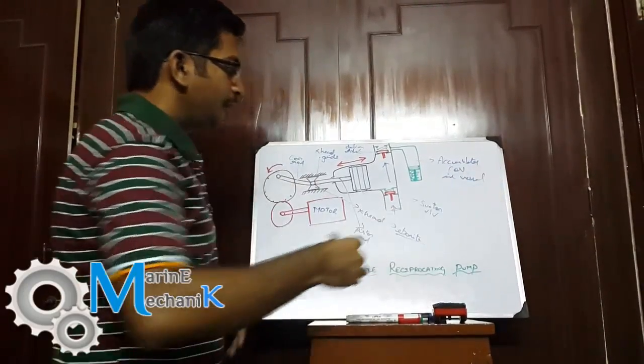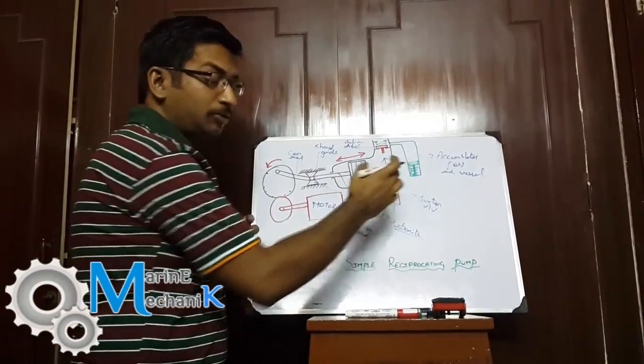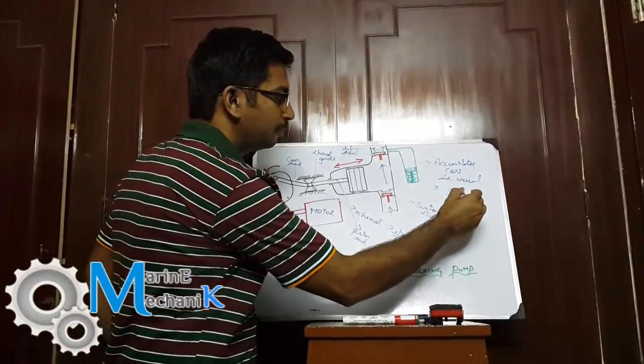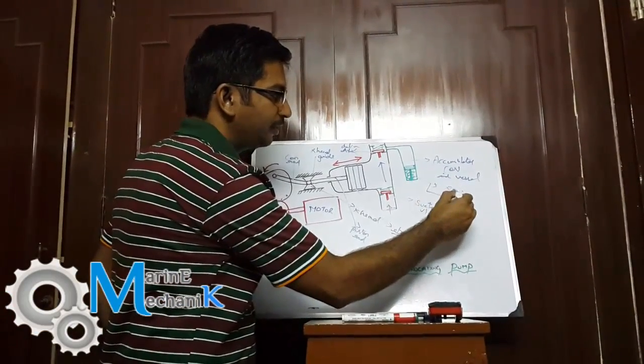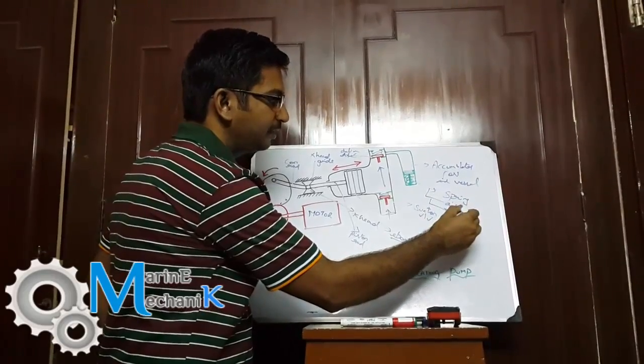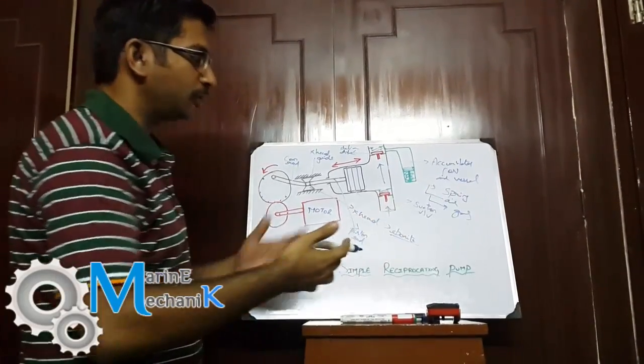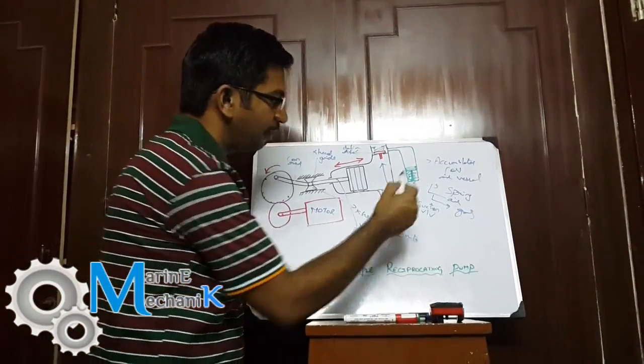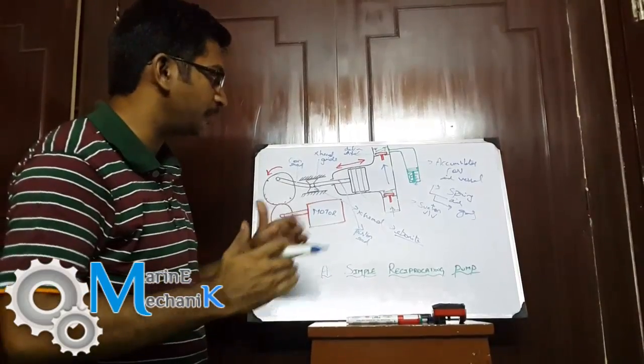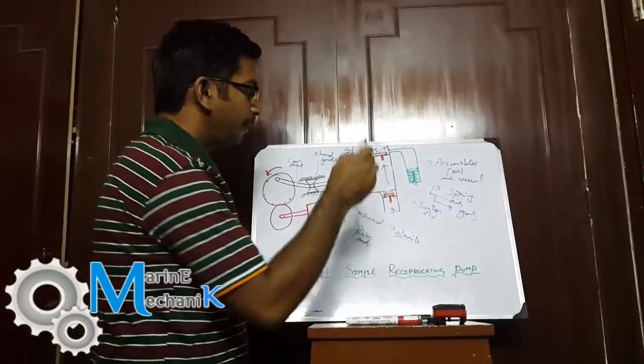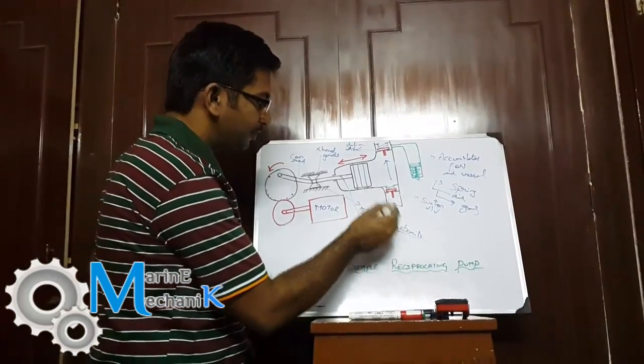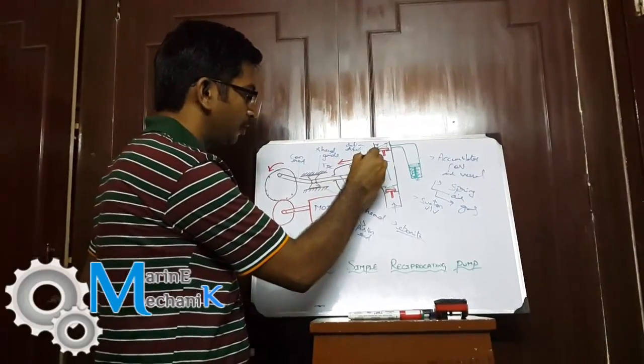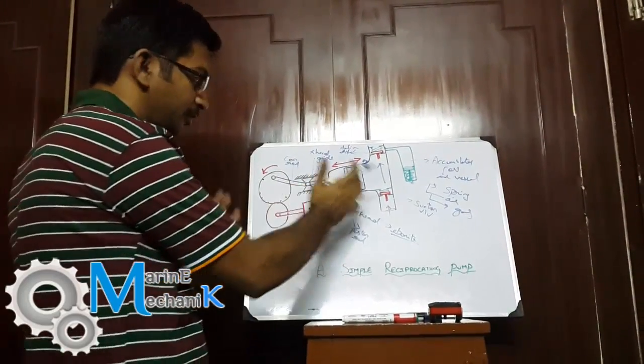There are two or three types of accumulator—one is spring loaded, other is compressed air, and other is gas charged. What I have drawn over here is spring loaded which has adjustable nut so that you can adjust the pulsations accordingly on the delivery line. Let me call this as top dead center and bottom dead center.